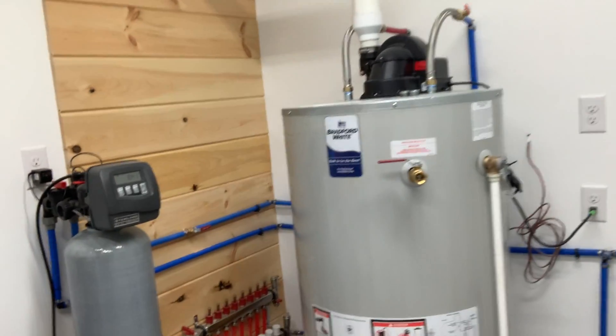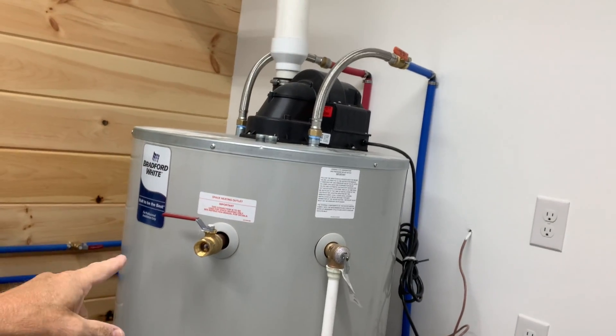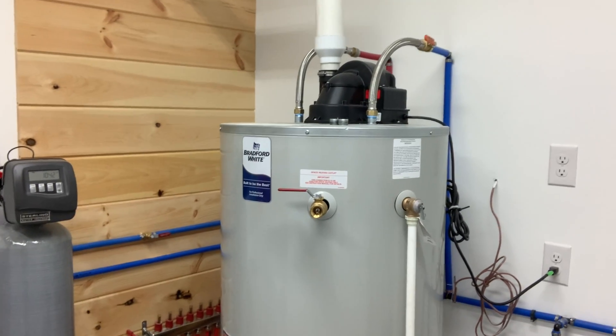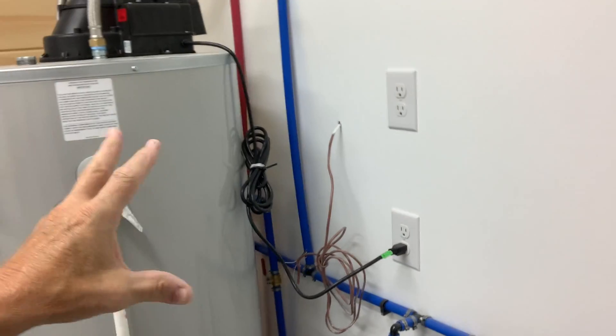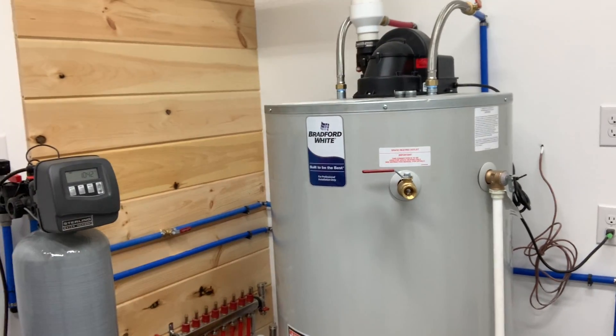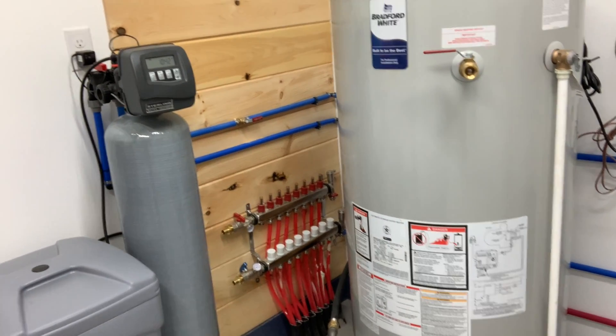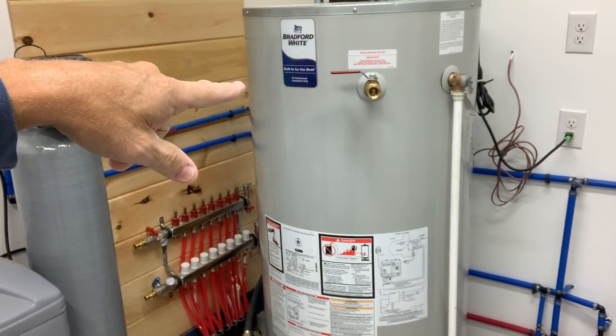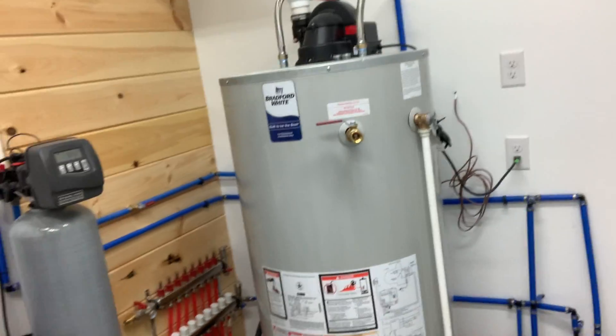I did buy a Bradford White 75-gallon hot water heater which has another feed and another return, and it says for space heater heating outlet, so it's got enough BTU. I'm going to use it for the in-floor because this is all hooked up for my hot water to supply the house. What I'm going to do is use a flat plate exchanger — I think I got a 50-plate — and that 50-plate will keep the water separate from the in-floor and the water that goes through the faucets. I will have a circulating pump on the hot water heater going through the flat plate, and then another pump heating from the flat plate to the in-floor.